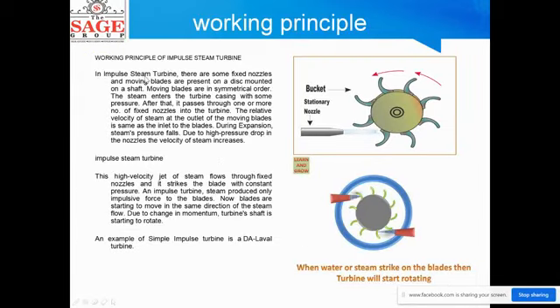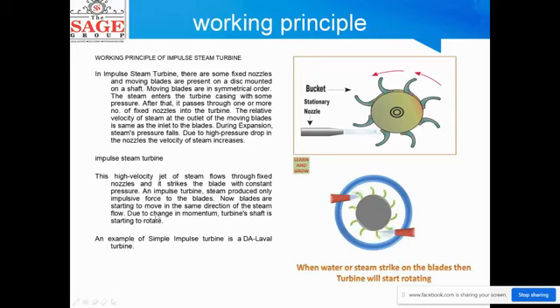Impulse turbine: In an impulse turbine, there are fixed nozzles and moving blades present on a disc mounted on the shaft. The moving blades are arranged in a symmetrical order. Steam enters the turbine casing with some pressure and passes through one or more fixed nozzles into the turbine. The velocity of steam at the outlet of the moving blades is the same as at the inlet. This is the impulse turbine — an example is the De Laval turbine. A high velocity steam jet flows through the fixed nozzle and strikes the blades at constant pressure. The impulse turbine steam produces only impulse force on the blades.